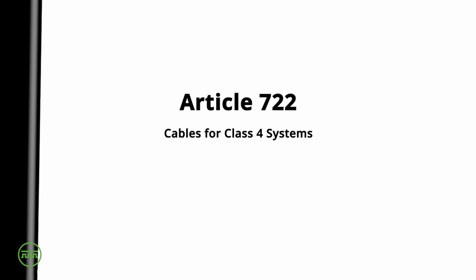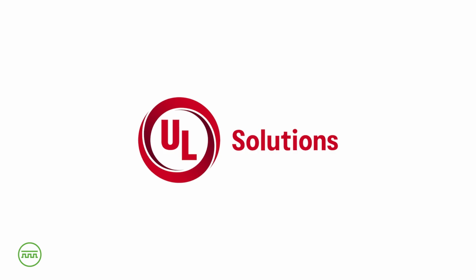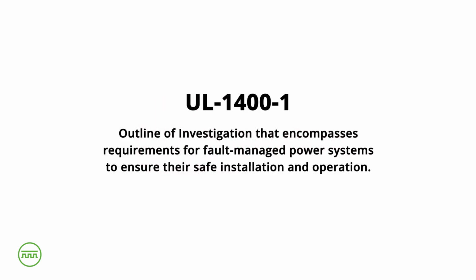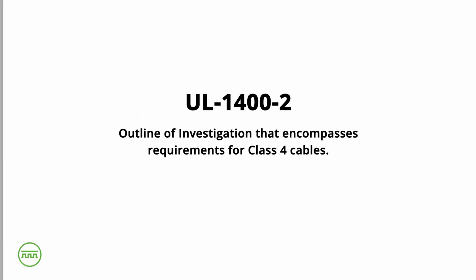Cables for Class 4 systems can be found under Article 722. To support new Article 726, UL, a third-party certification company, has also been working behind the scenes to prepare for Class 4 systems. It recently published UL 1400-1, an outline of investigation that encompasses requirements for fault-managed power systems to ensure their safe installation and operation. It also published UL 1400-2, an outline of investigation that encompasses requirements for Class 4 cables.